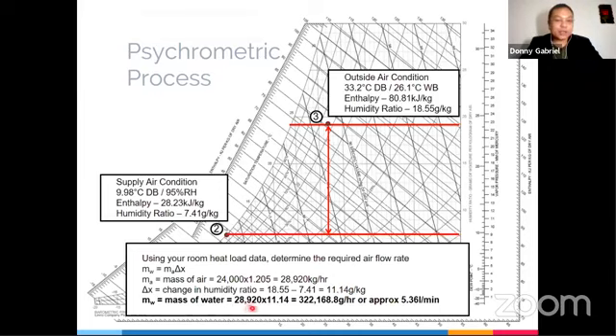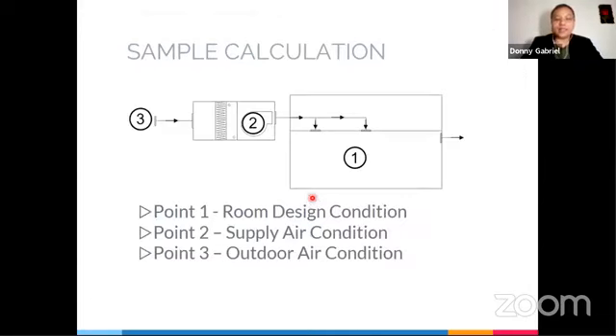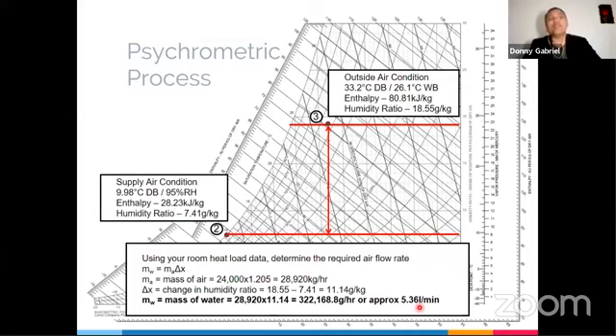So mass of water is equal to 28,000 kilogram times 11.14. It will give you an approximation of 5 liters per minute. So this air handling unit, or this aircon, is condensating or giving you condensate water of approximately 5 liters per minute. So you'll be able to determine your pipe size already based on this flow rate.